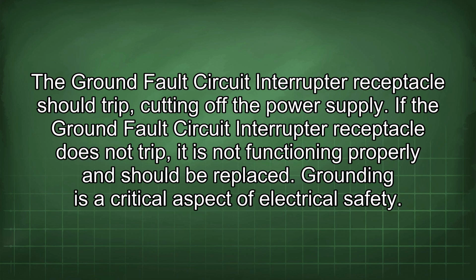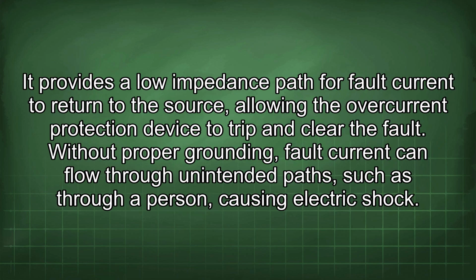Grounding is a critical aspect of electrical safety. It provides a low impedance path for fault current to return to the source, allowing the overcurrent protection device to trip and clear the fault. Without proper grounding, fault current can flow through unintended paths, such as through a person, causing electric shock.